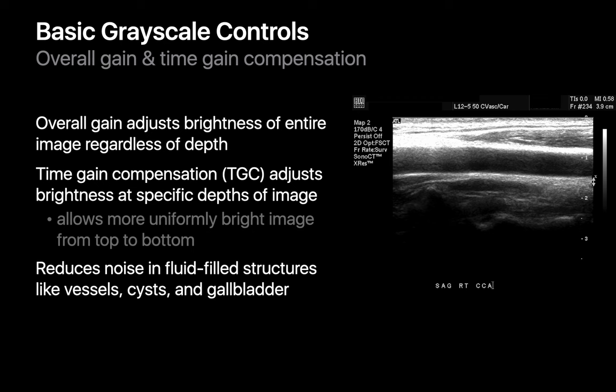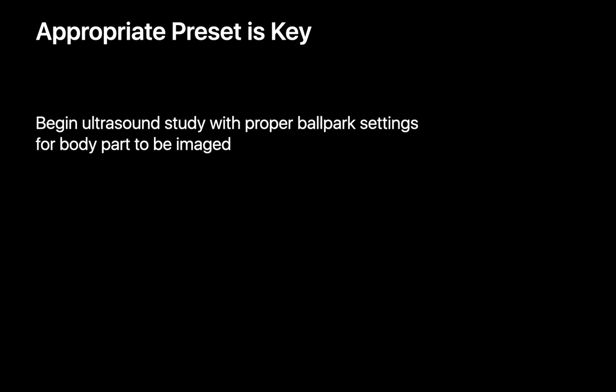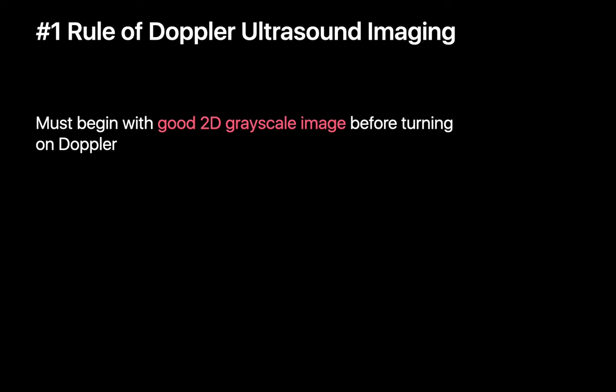Gain refers to the brightness of your 2D grayscale ultrasound image. The brightness of the entire image can be adjusted using the overall gain control, but brightness can also be adjusted at specific image depths using the time gain compensation controls, which looks like the graphic equalizer on a home stereo system. By tweaking overall gain or gain at specific depths, you'll reduce image noise and create an easier image to interpret. A reminder: good color Doppler imaging depends on a good 2D grayscale image, so take the time to optimize your 2D image before switching on Doppler.